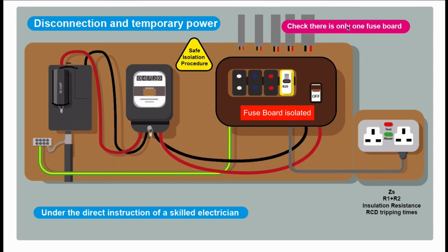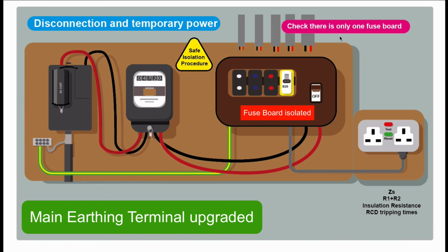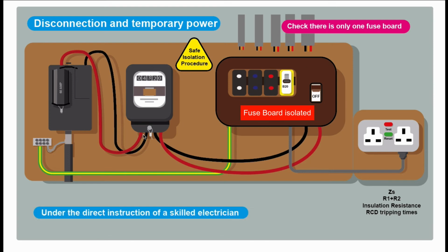Cables right out of the fuse board, we know that there's no power in these cables anymore. But just double check that there's only one fuse board, because you'll have people working in the house who are not electrically skilled. They won't be testing stuff, they'll just be chopping through things and pulling things down and ripping things out. So you want to be 100% sure that there's no power left anywhere in the house apart from in this area. So just have a good walk around, make sure that everything is disconnected. There's no other fuse board which might be powering something.